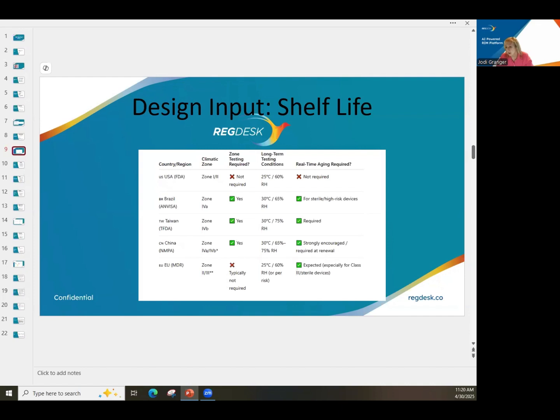in the development process. But they're critical to understand on the front end because shelf life takes a long time. And so it's important to understand where you're going to sell and make sure that the testing that's being done on these products is going to meet the need for each of these markets. This is just one example of an area that if you factor this into your design input document, then you'll make sure that you're covered. And it's really critical for the success or overall launch of a product to get to this level of detail in your plans and in your design input.